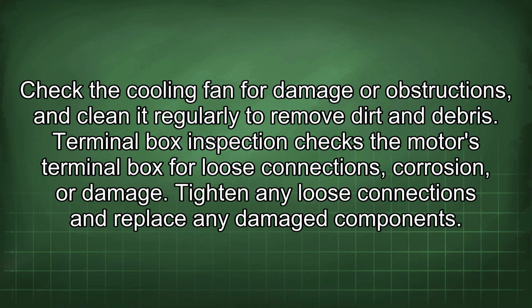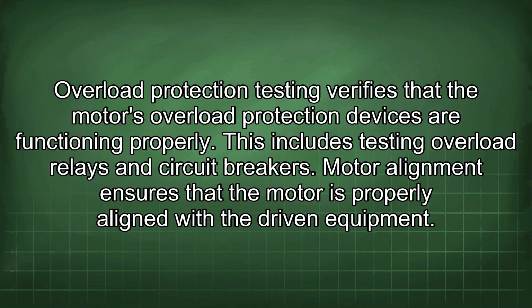Terminal box inspection checks the motor's terminal box for loose connections, corrosion, or damage. Tighten any loose connections and replace any damaged components. Overload protection testing verifies that the motor's overload protection devices are functioning properly. This includes testing overload relays and circuit breakers.